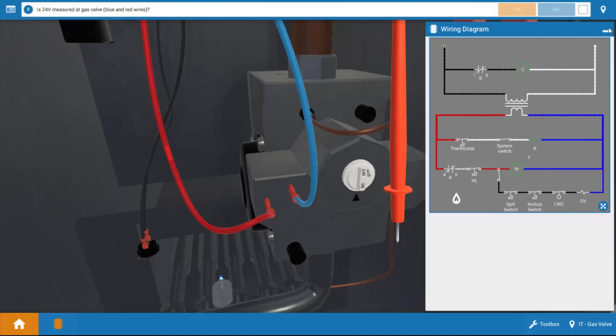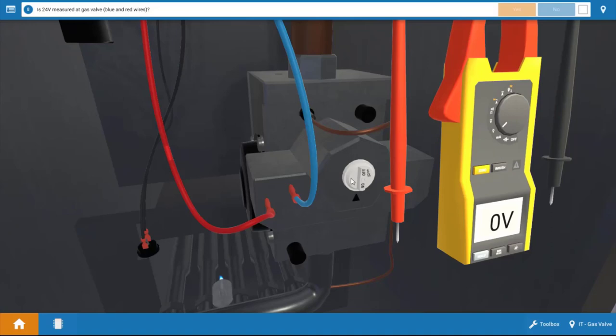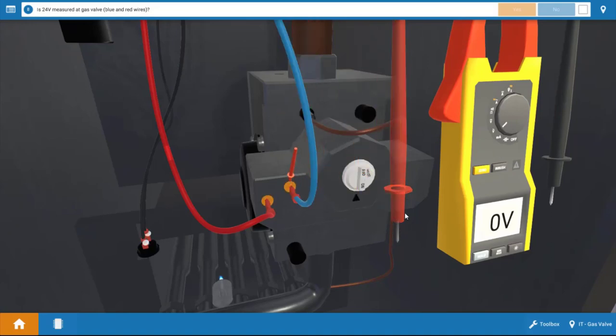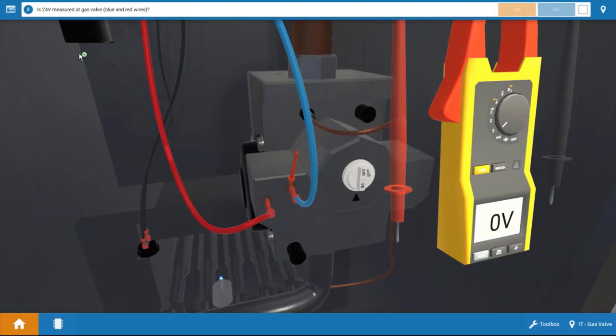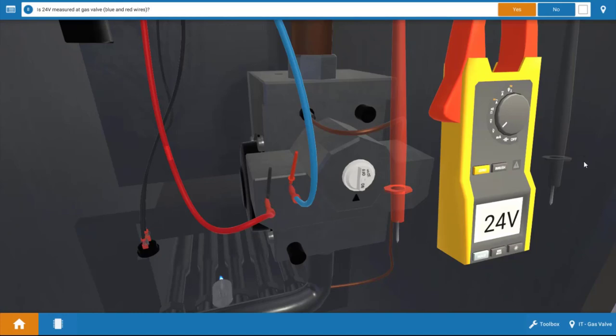So probably the easiest thing to do is measure for 24 volts at the gas valve. So let's store the wiring diagram away. And we're going to take the leads and place them at the coil connections or solenoid connections at the gas valve. And when we do this, we can see we have 24 volts at the gas valve.